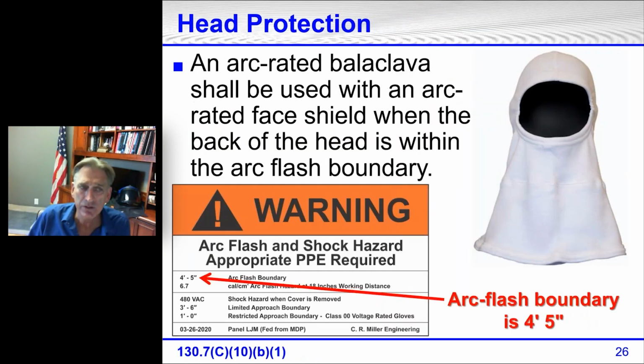An arc-rated balaclava has to be used with an arc-rated face shield when the back of the head is within the arc flash boundary. A while ago I said you might have a hard hat with face shield and maybe an arc-rated balaclava. On this equipment label, the arc flash boundary is 4 feet 5 inches. Is the back of your head going to be in the arc flash boundary? Yes, it is. I've seen labels where the closest arc flash boundary I have ever seen was 2 inches. Well, the back of your head's not going to be in the arc flash boundary when it's 2 inches or 6 or even 12 or so.